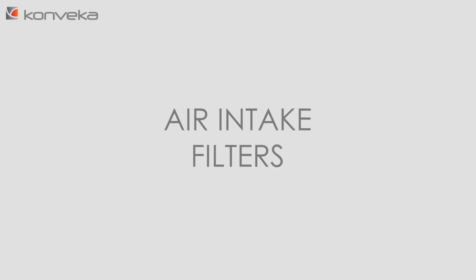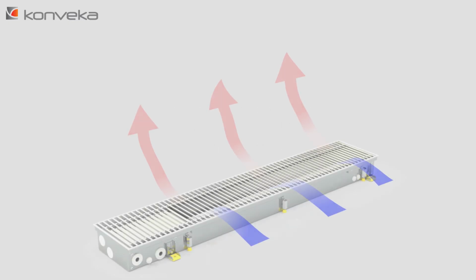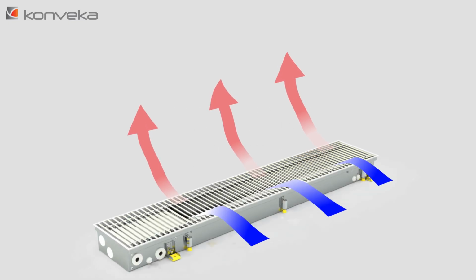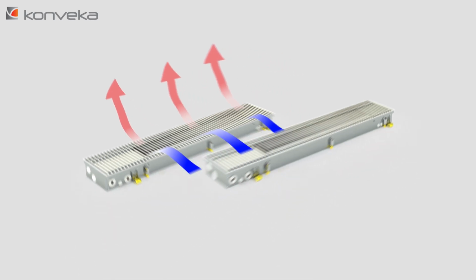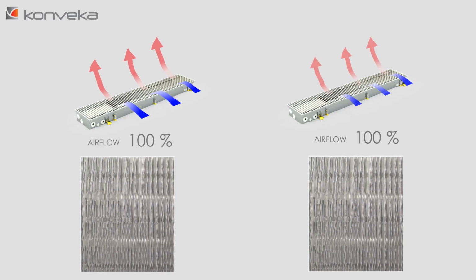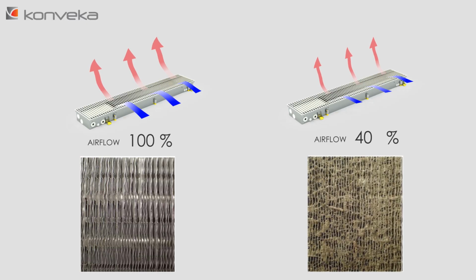Air intake filters. The quality of the air passing through the convector has a profound effect on the service life and operational quality of the appliance. When the convector is running, the fans draw in the ambient air and push it through the heat exchanger. Uncleaned air passing through the heat exchanger contaminates it with dust, animal hair, and fine debris, which rather quickly is followed by a significant reduction in the amount of air passing through the heat exchanger and, consequently, the output of the appliance.